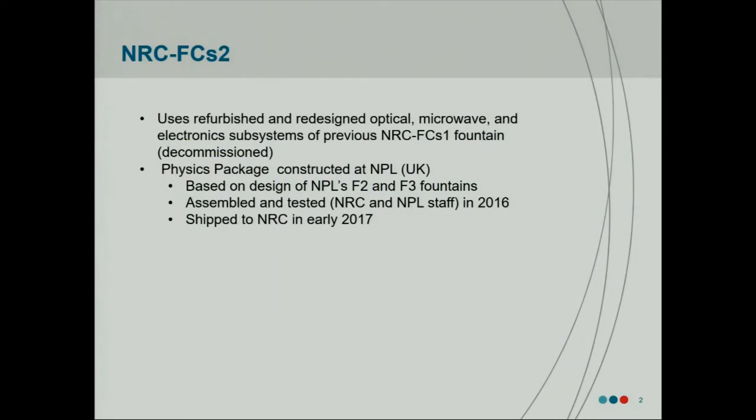FCs2 uses refurbished subsystems from our previous fountain, NRC-FCs1 — the optical system, the electronic system, and the microwave system — they've all been basically redesigned and upgraded. The physics package for FCs2 was actually designed and built at NPL. This was a commercial and scientific collaboration where NPL were contracted to build a physics package for us based on the design of their F2 and F3 fountain clocks. During the construction and testing, NRC staff went over to help with the assembly and testing before it was shipped to NRC, under vacuum across the Atlantic — and it arrived under vacuum as well. That arrived in early 2017, and since then we integrated it with our other systems. Within a few months we were able to get Ramsey fringes and start to evaluate the performance of the entire system as a whole.